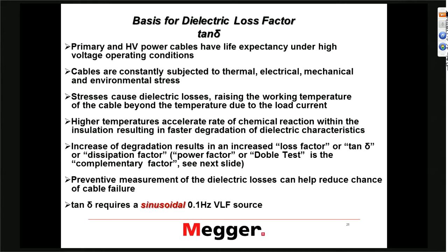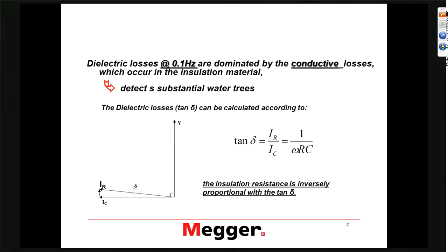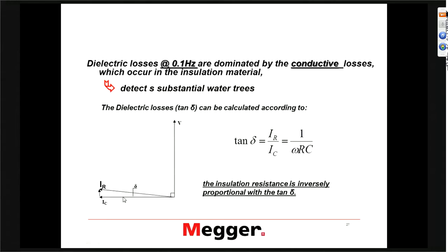We cannot use a cosine-rectangular angular wave shape for Tan Delta testing. This shows the loss angle: when you do power factor testing you look at this angle, and for cable testing we look at this angle — basically the ratio of the resistive and the capacitive losses. If aging takes place, we get more and more resistive losses. That's why the Tan Delta goes up.